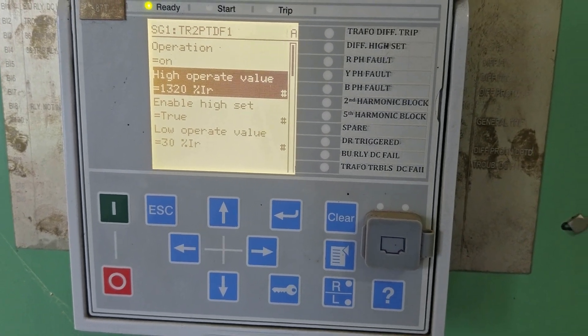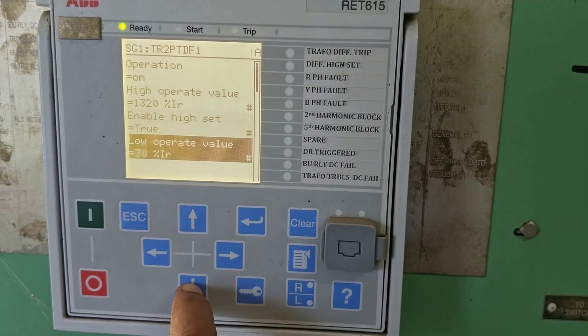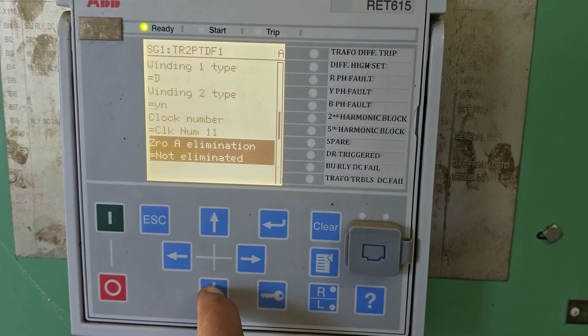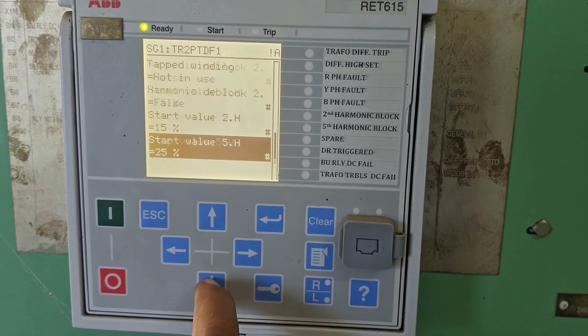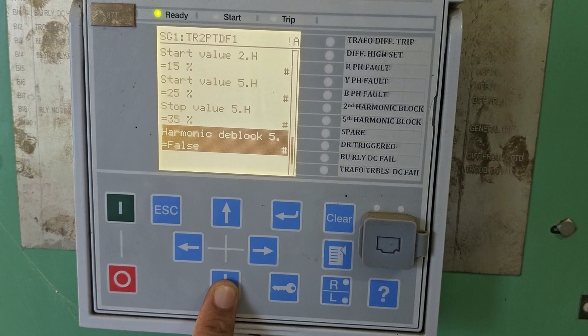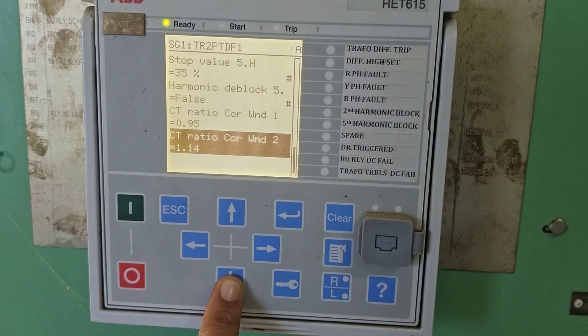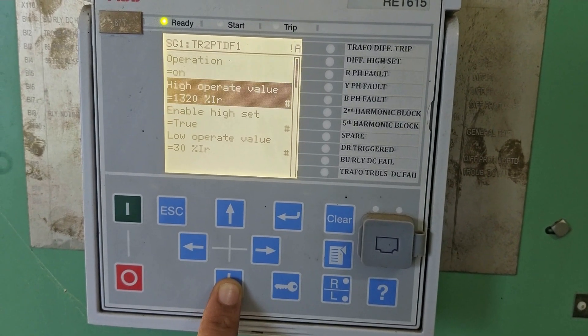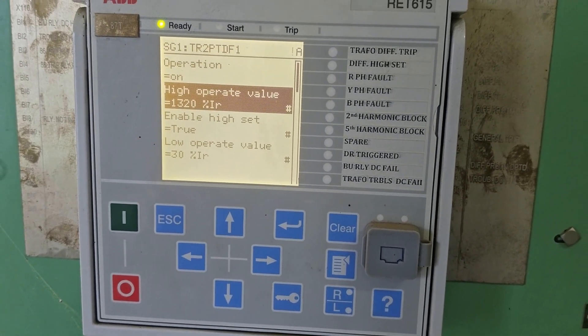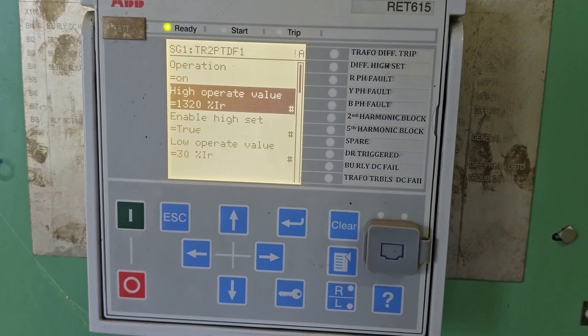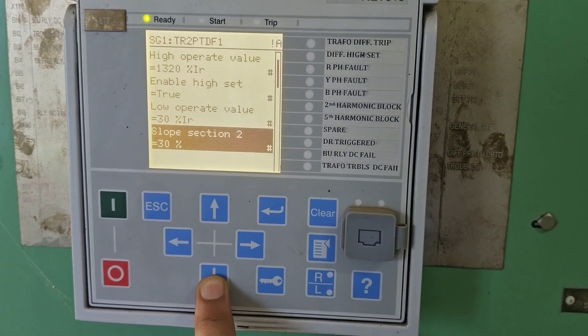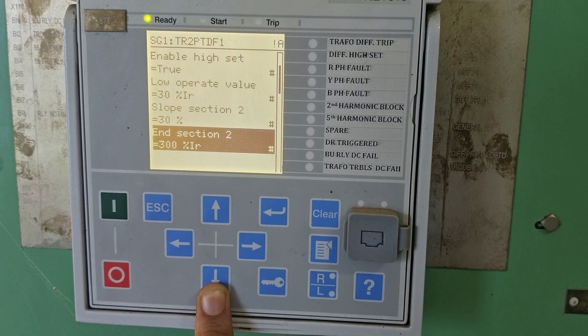First of all, the operation is ON and the high operate value is 1320% of Ir — that is 1320% of the rated current. If the differential current exceeds or comes to 1320%, the transformer will trip immediately. That is the high set value, indicating the transformer is at very high risk and has a severe internal fault or severe winding fault.